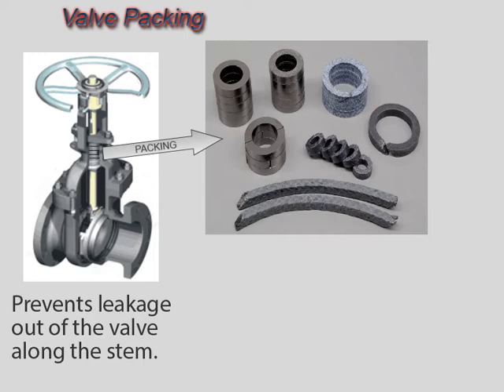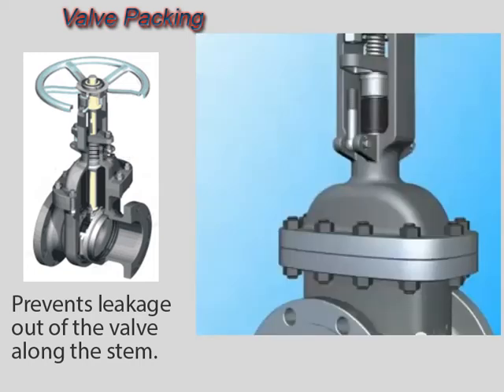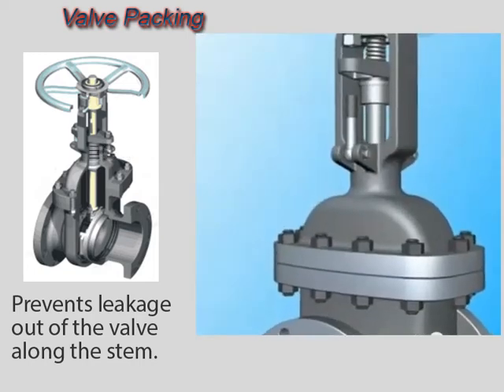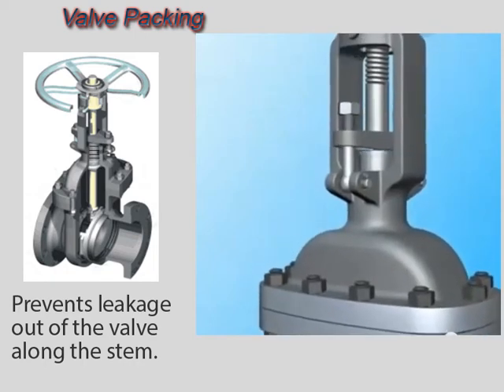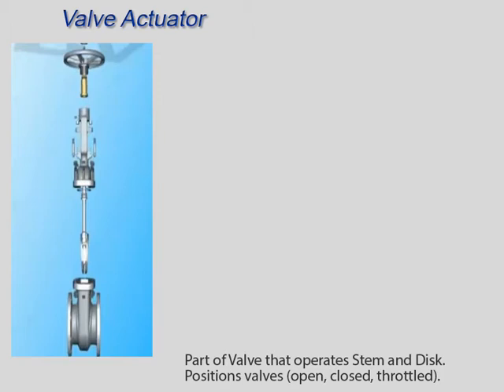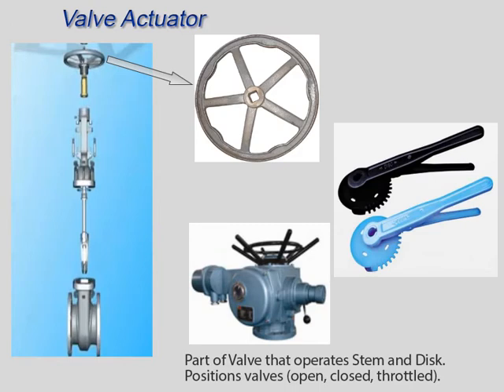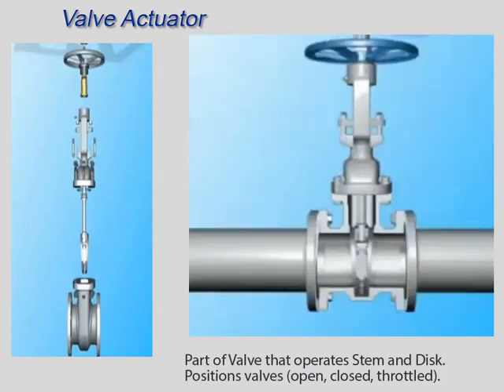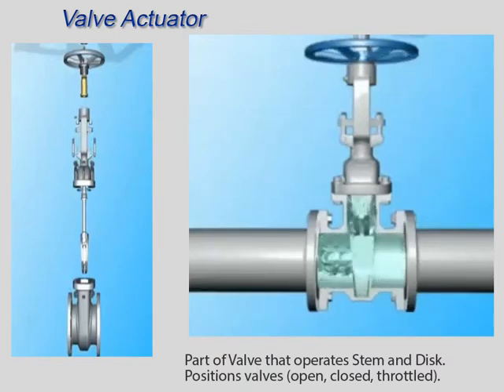Valve packing must be properly compressed to prevent fluid loss and damage to the valve's stem. If a valve's packing is too loose, the valve will leak, which is a safety hazard. If the packing is too tight, it will impair the movement of, and possibly damage, the stem. The actuator is the part of the valve that operates the stem and disc assembly. There are many actuator designs available — it may be as simple as a manual handwheel or as complex as a motor. The purpose of actuators is to position valves open, closed, or throttled. The positioning of the valves can be done manually or automatically, and the operation can be performed locally or remotely.